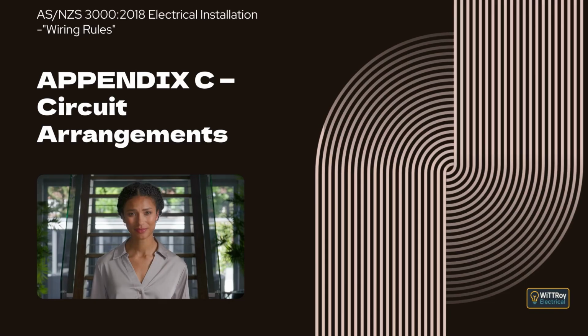Clause C2.3.2.1, Example 1. This example explains how to determine the maximum demand of a single domestic installation supplied at single phase. Different types of loads such as lighting, socket outlets, fixed appliances, heating, and special loads are grouped and assessed using the diversity approach. The individual group demands are then added together to give the total maximum demand for the installation.